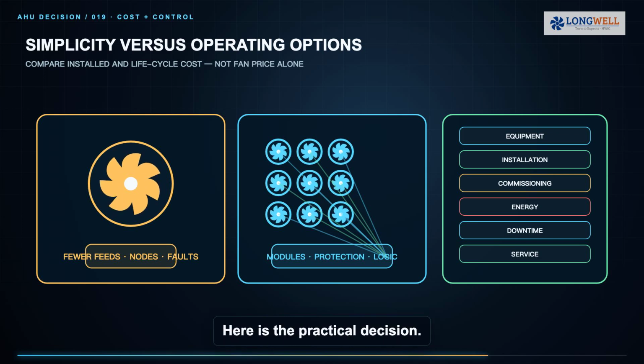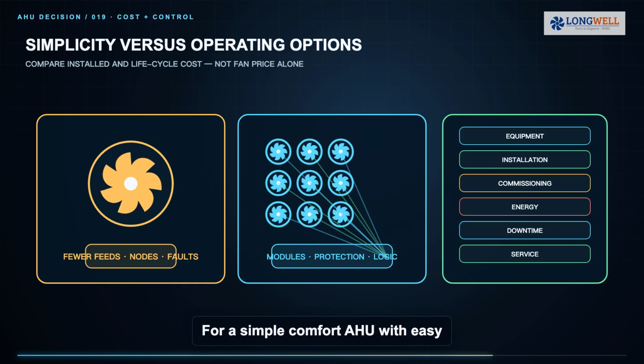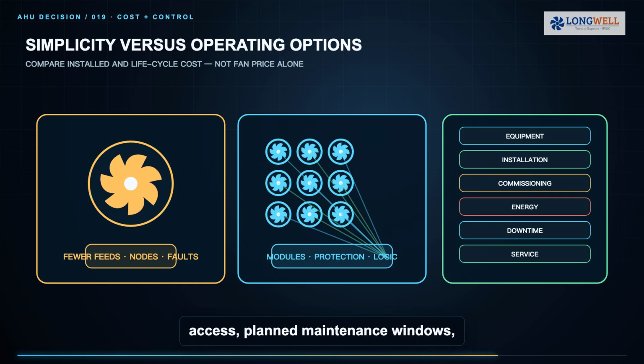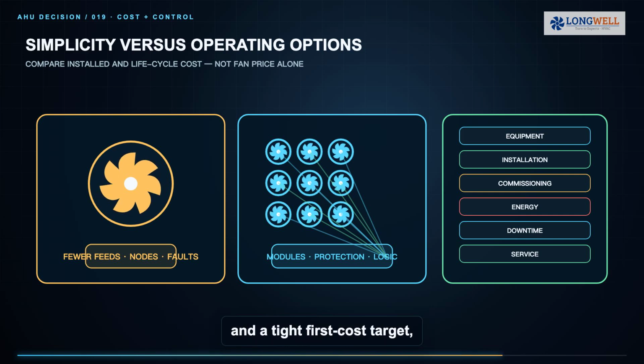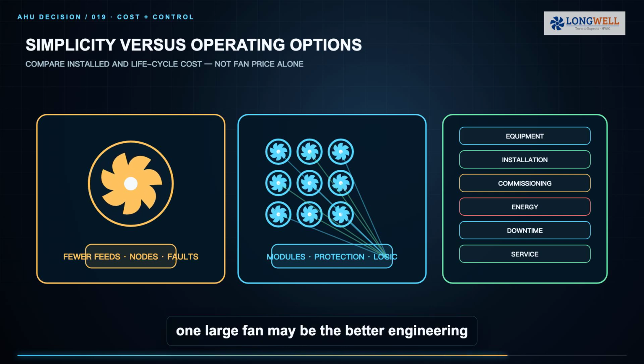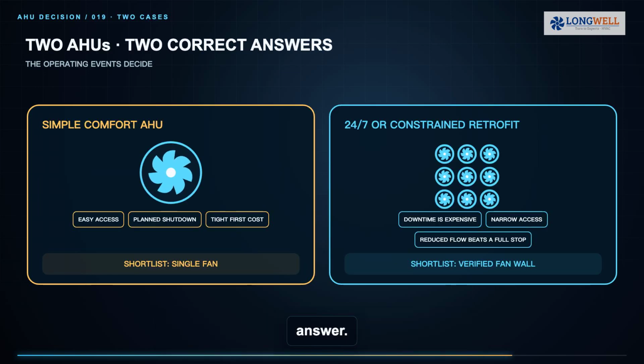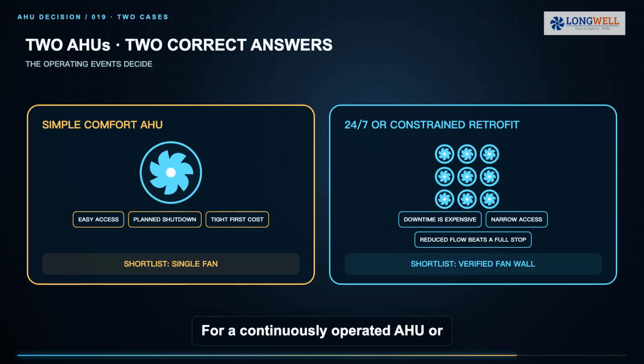Here is the practical decision. For a simple comfort AHU with easy access, planned maintenance windows, and a tight first cost target, one large fan may be the better engineering answer. For a continuously operated AHU or CRAH, a constrained retrofit, or a process where reduced airflow is preferable to a full stop, a verified fan wall deserves the shortlist.